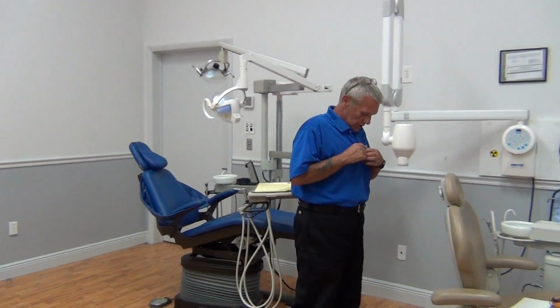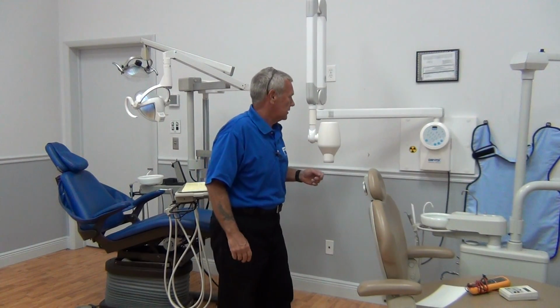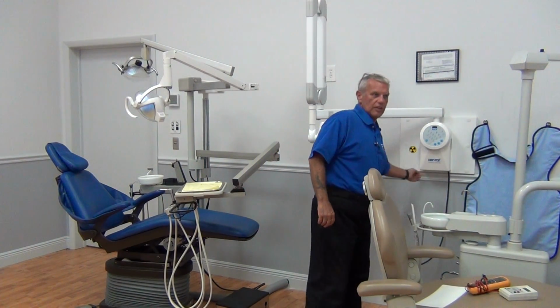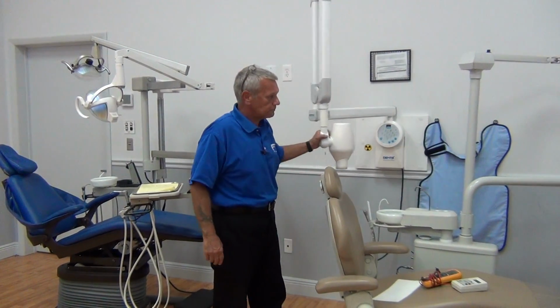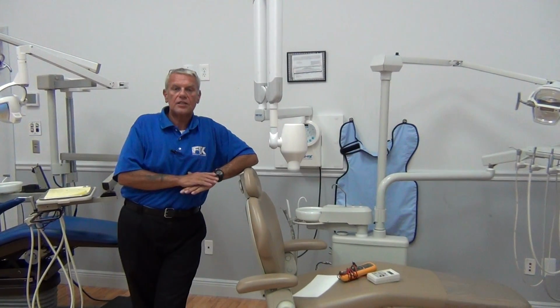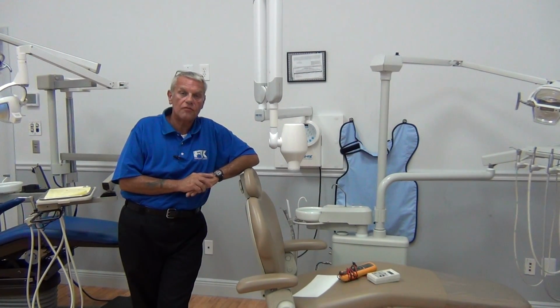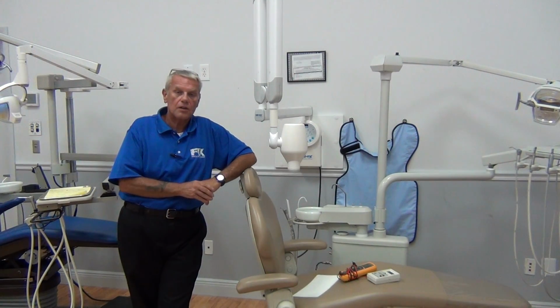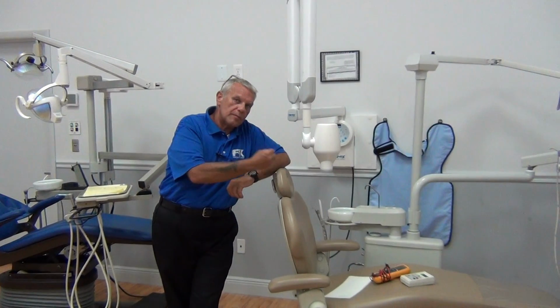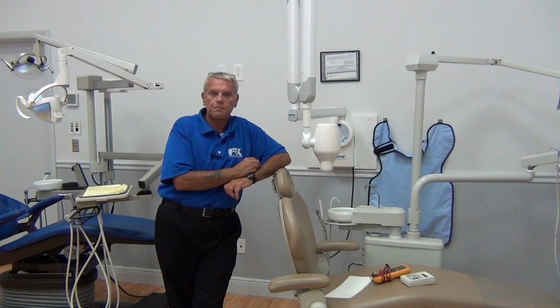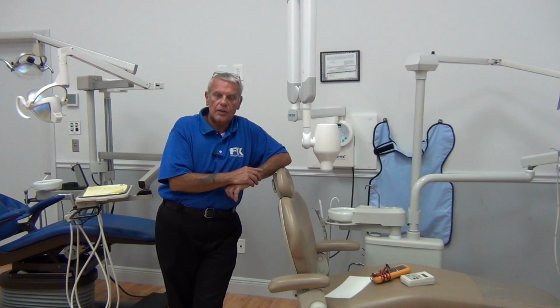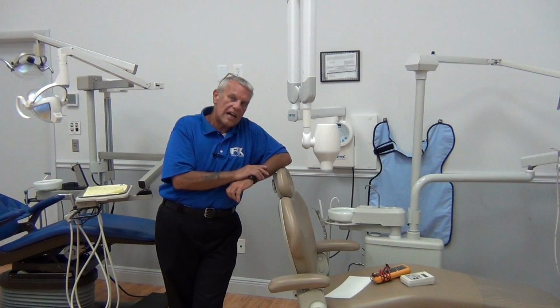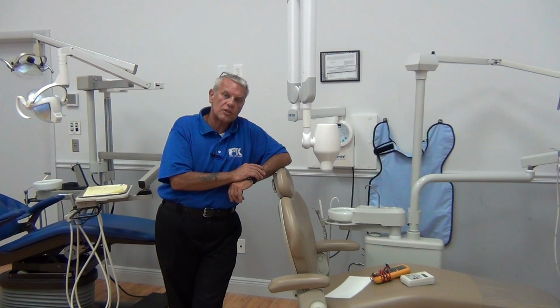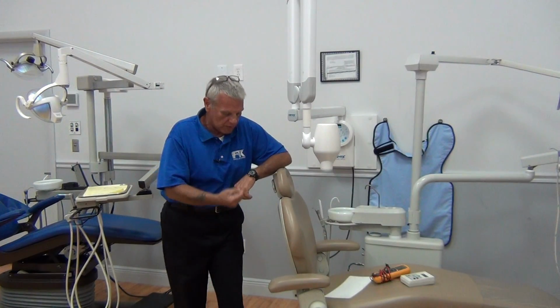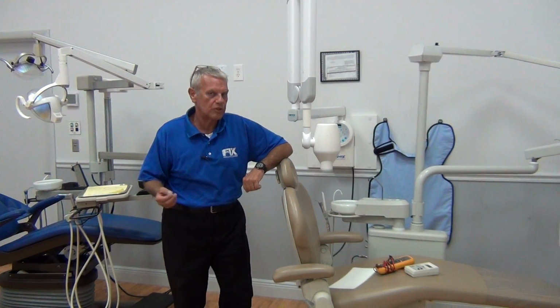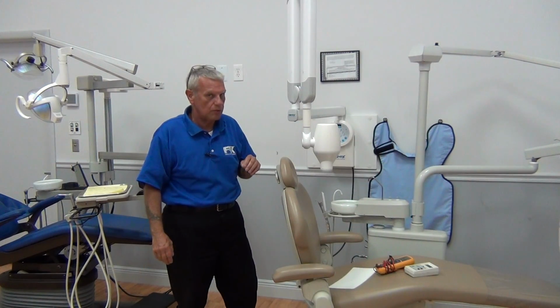Our first calibration, our first check, is going to be a drift check. When we say drifts, we mean movement of the x-rays as we all learned in x-ray class. We're going to actually have a good chance to interact with the office staff and to get to know the office staff where you're doing the inspection. The correct protocol is to call the assistant who makes the x-rays into this room, and ask her to raise the chair where she usually makes her x-rays, which is usually a higher position. There's an exam position and an x-ray position. Let her come up and customize the chair and raise it to where she usually uses it. That puts her in the process, and it also is very valuable for you.